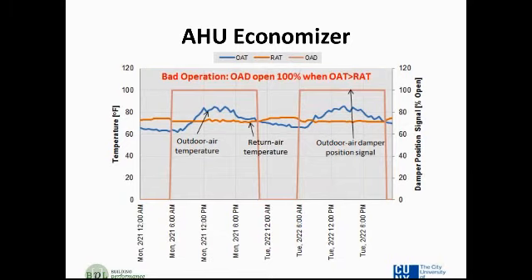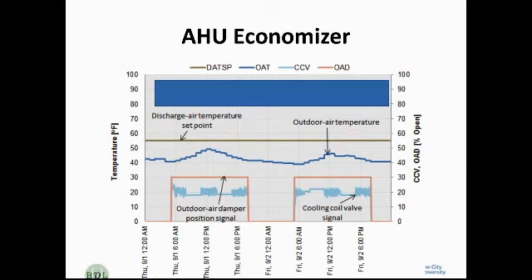So again, by using building retuning, we tell you which parameters you need to be tracking and trending in order to find out where these opportunities are. And within the measures, in fact, in the economizer questionnaire that's part of the building retuning measure, I think it gets into 11 or 12 different questions, different things to look for. Very useful material. So that's bad operation. We can see that the outdoor air damper is way too far open, and we're having to cool down that outdoor air more than the return air.